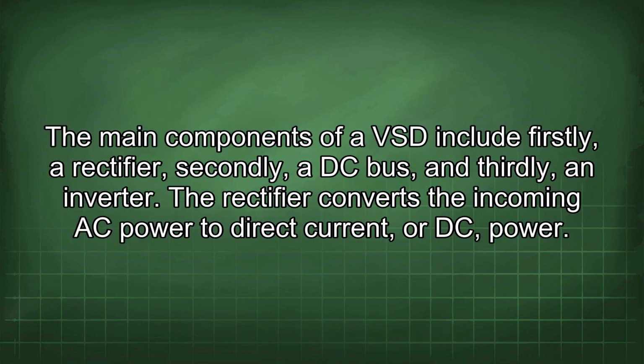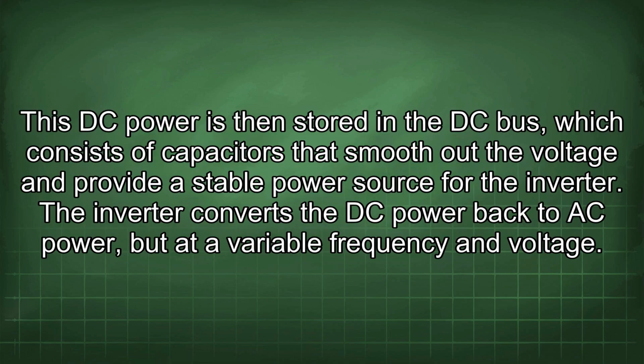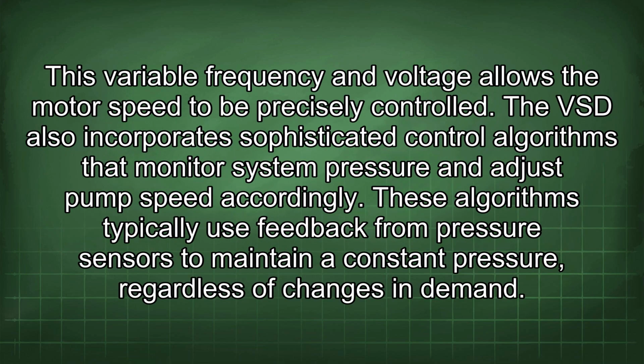The main components of a VSD include firstly, a rectifier, secondly, a DC bus, and thirdly, an inverter. The rectifier converts the incoming AC power to direct current, or DC power. This DC power is then stored in the DC bus, which consists of capacitors that smooth out the voltage and provide a stable power source for the inverter. The inverter converts the DC power back to AC power, but at a variable frequency and voltage. This variable frequency and voltage allows the motor speed to be precisely controlled.